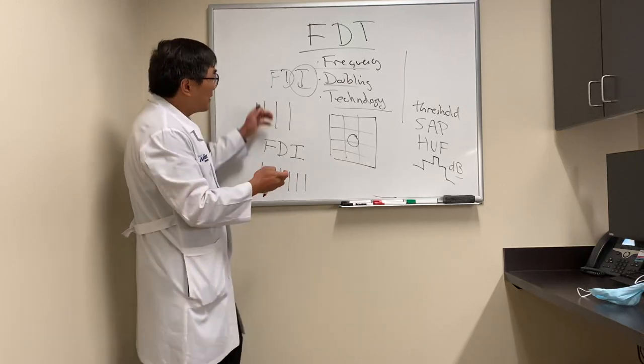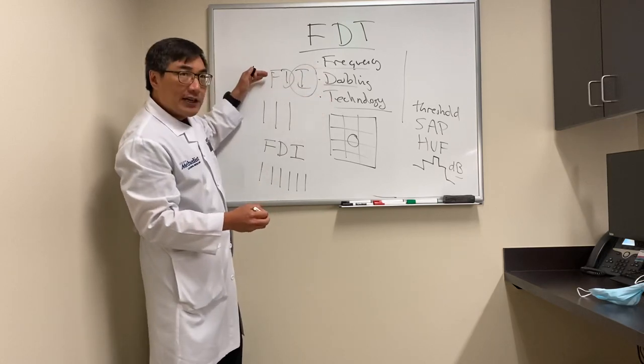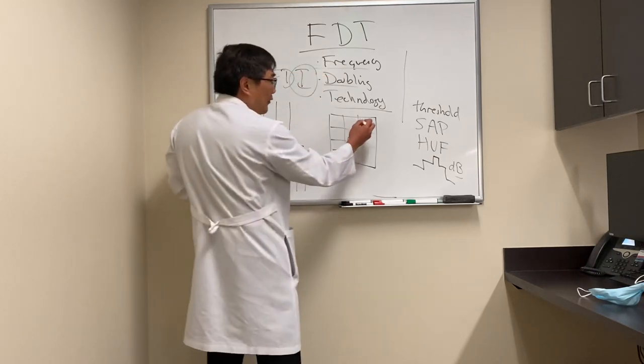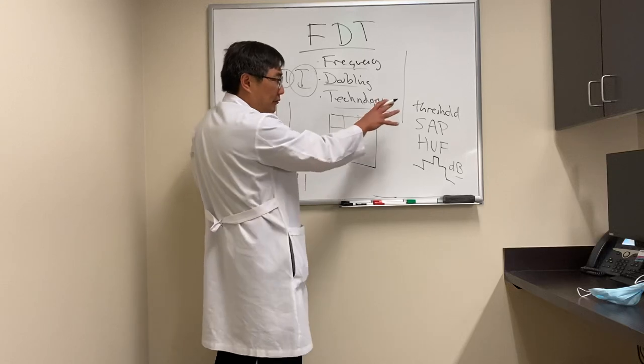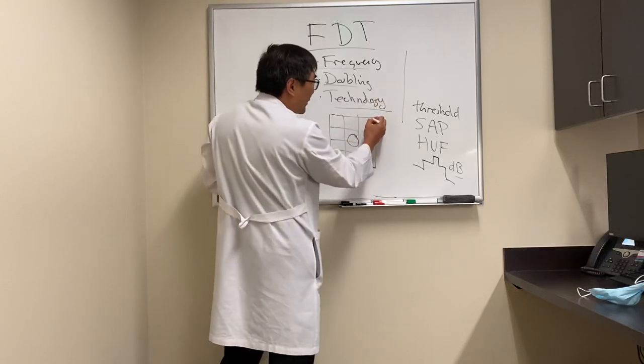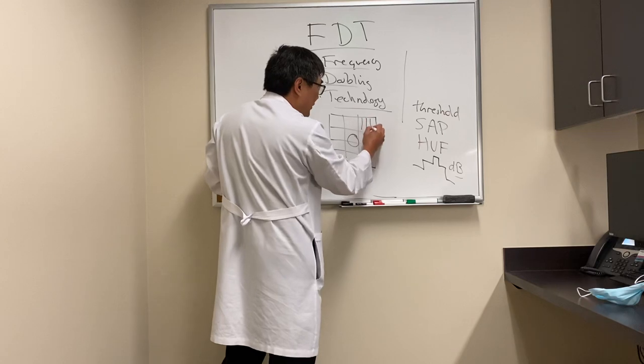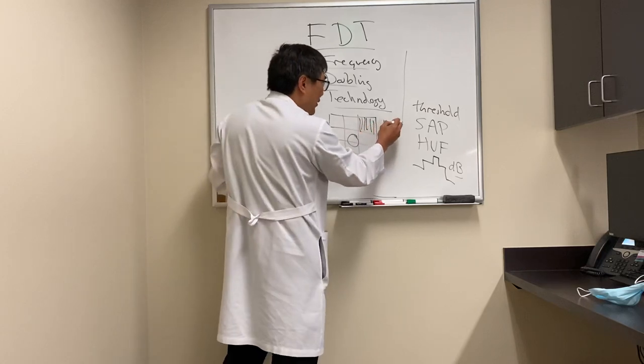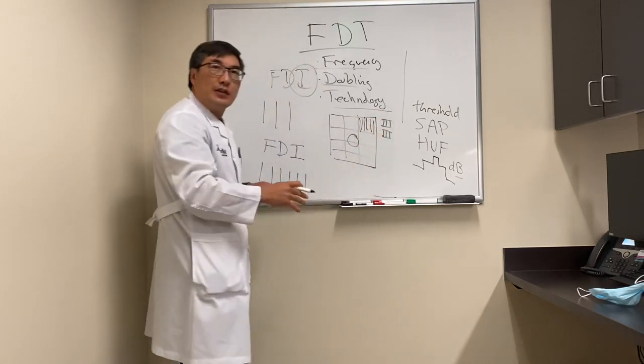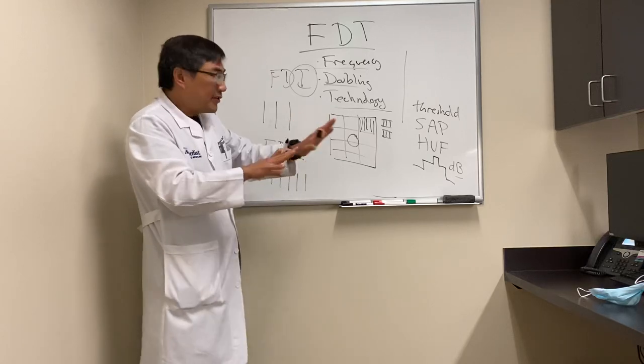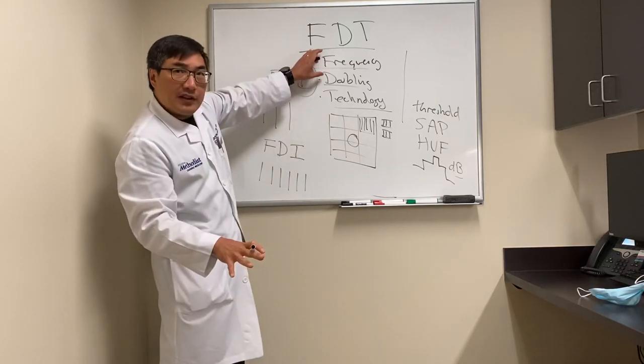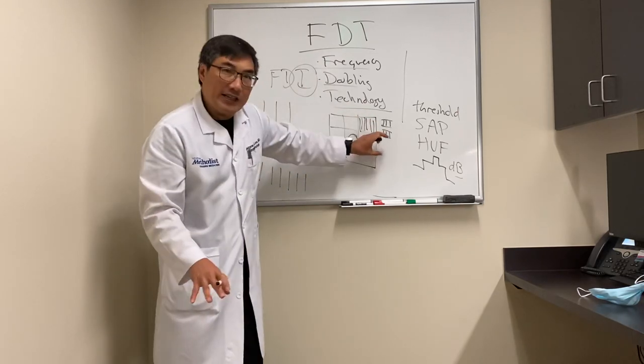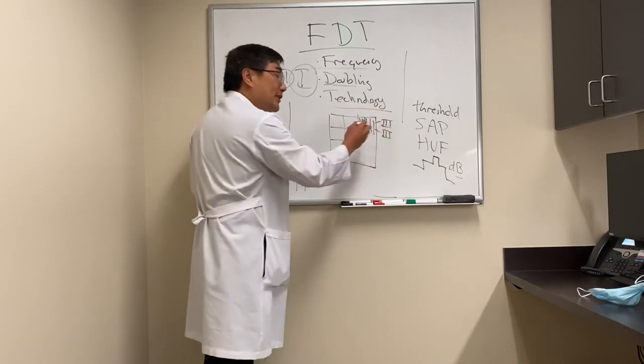In FDT testing, you're taking advantage of the frequency doubling illusion. By changing the frequency, we can induce a doubling illusion. When testing this square — analogous to testing a spot on Humphrey visual field — the patient will see six of these gratings, even though it's really just a combination of two different sets of three that are counterfacing. That flicker is what creates the illusion of six, even though there are only three. That is frequency doubling technology.